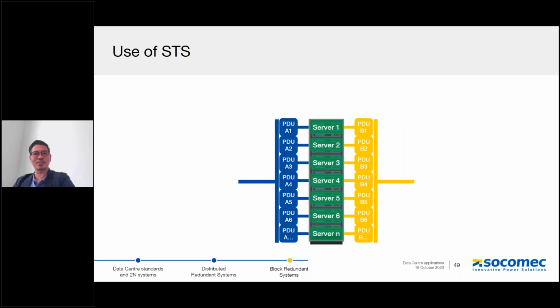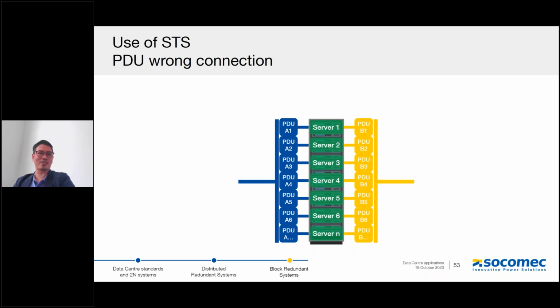Internally, we know servers have dual power supply, and there's a possibility of a PDU failure that affects all the servers connected. This causes a downgrade of reliability or availability on one source, putting that server into downgrade mode since it's only getting power from one source. There's also a possibility that the PDU or server is connected to the wrong PDU, so even though it has two outlets or two inputs, they're connected to the same source. This creates a point of failure that can also bring the server down. These things happen typically in data centers if you don't have proper workflows or proper control in installation or data center management.